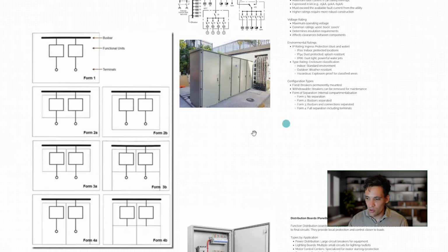Or you could have a Form 2, which means the bus bar is separated from the circuit breakers, a Form 3, where the bus bars are connected, where the individual circuit breakers are separated, or you can have a Form 4, which means the entire facility, including the terminals, is all in separate compartments, and so it's safe to perform maintenance on without isolating the entire board.